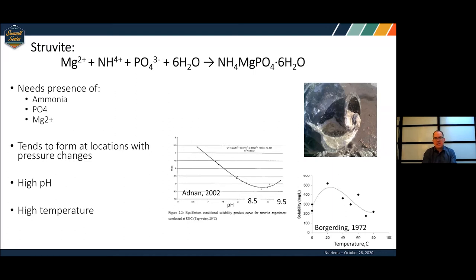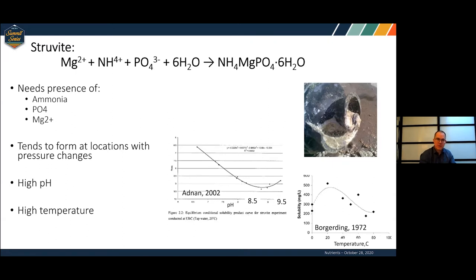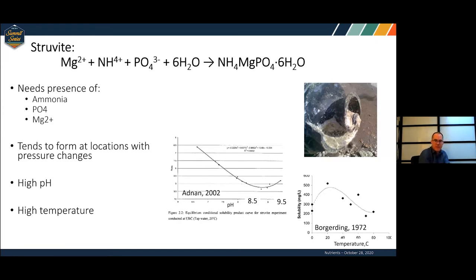Before I dive into the balance, a little background on struvite. Struvite is a precipitate that forms when three things are present: ammonia, orthophosphate (PO4), and magnesium. When these three are present in the right conditions, it forms a precipitate. It tends to form at places where pressure changes — think pumps, pipe elbows, impellers, mixers. It prefers high pH, with a sweet spot around 8.5, and prefers higher temperatures as well.